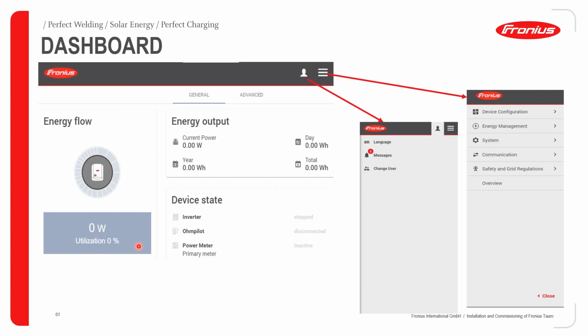Good. And then when you finally have access to the dashboard, you will be able to access your profile with this headshot. Clicking on the headshot gives you access to your profile where you can change the language, access your messages if there are any, and change user. Let's say you're an installer or a technician using the technician access level, and you finish installation and wouldn't want the customer to have access to sensitive grid settings. You could change the user here and replace it with the customer access level. Then clicking on the menu button gives you access to the device configuration and other settings such as energy management, system settings, communication, safety, and grid regulations.